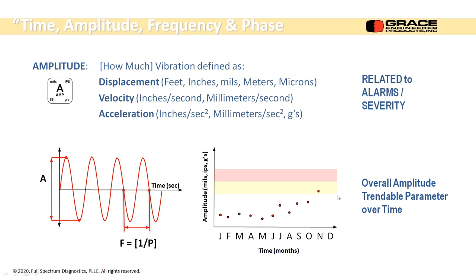I don't want to use 0.35 inches per second if I'm running at 0.1 all the time. I want to know how big and how fast it changes from 0.1 to 0.15 or 0.1 to 0.2. If I had this type of alarm set too high, I might miss something like that. So that's the greatest thing about these transducers: they stay in one place all the time and they're constantly taking data, with no human interaction to bother them.